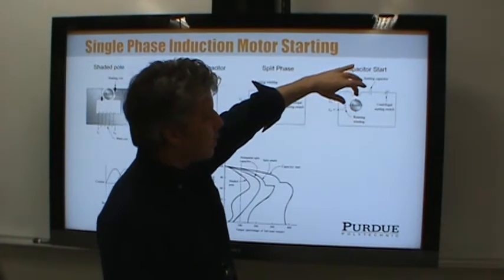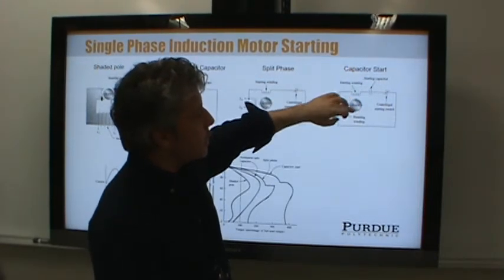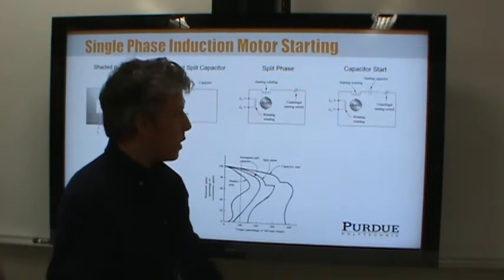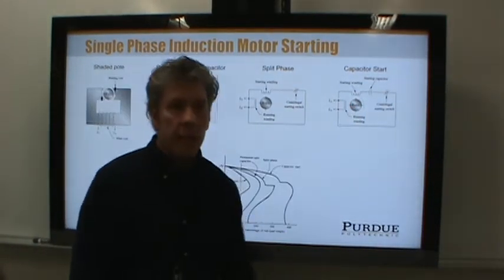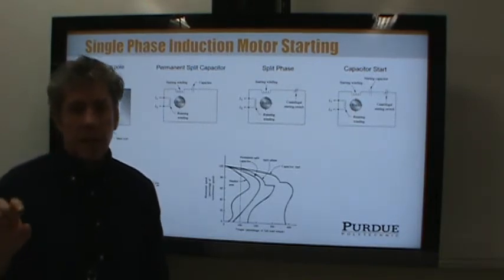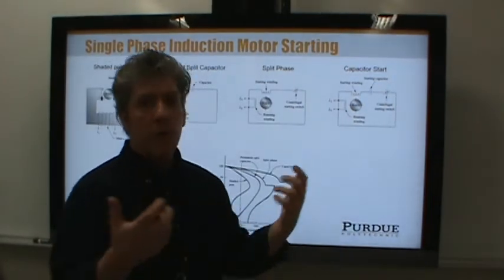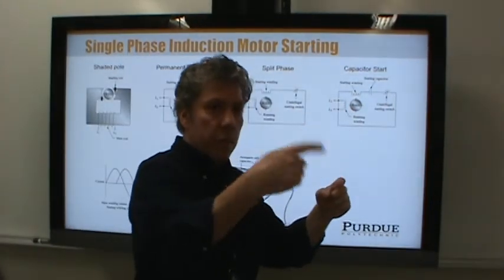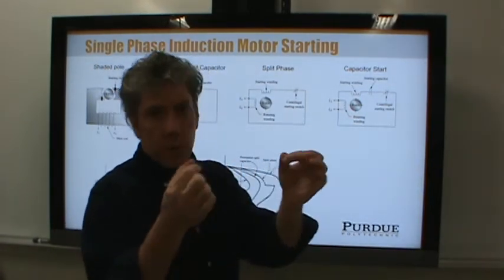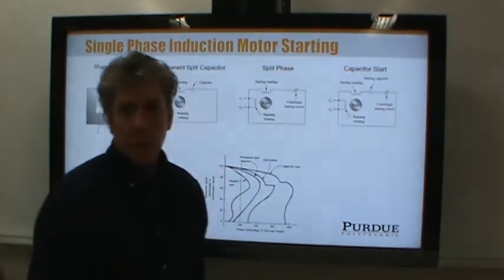By using these two windings, you can generate torque in one direction so the rotor starts rotating in the desired direction. The starting capacitor helps kick it and get it started. Once the rotor starts turning, a centrifugal mechanism mounted on the rotor throws out its arms and pushes against a switch to shut off the start winding and start capacitor.